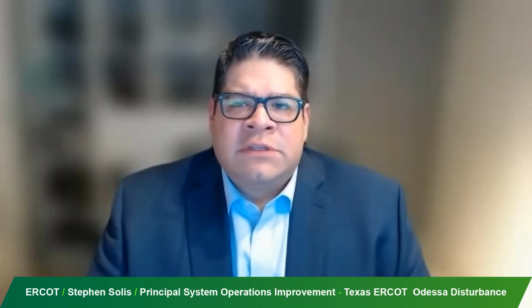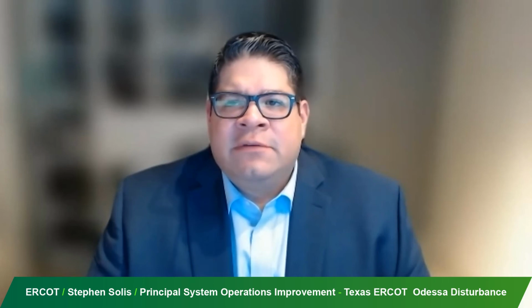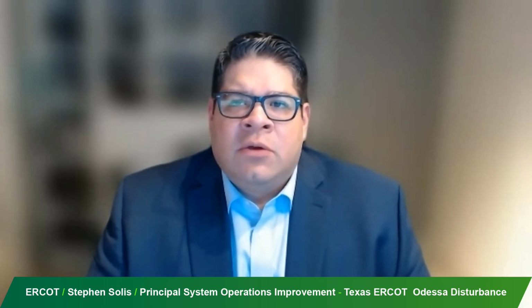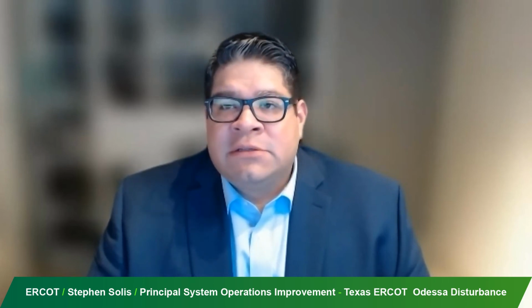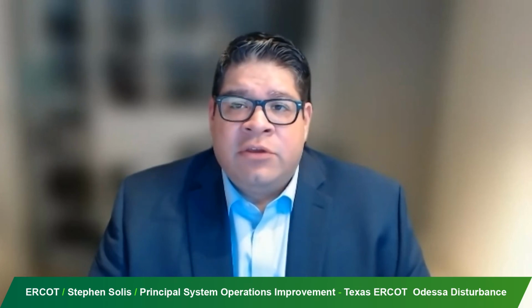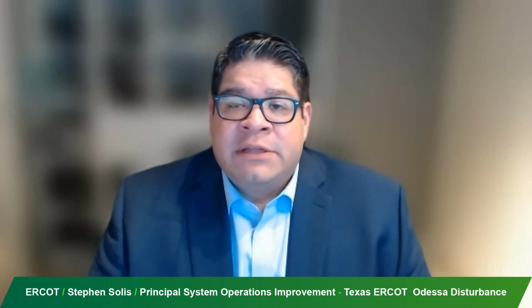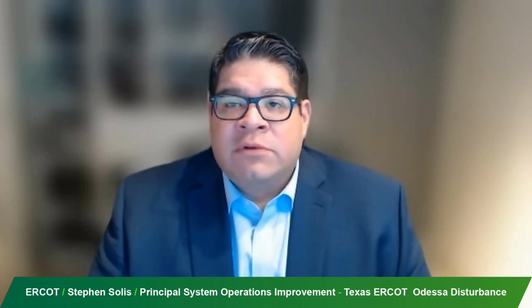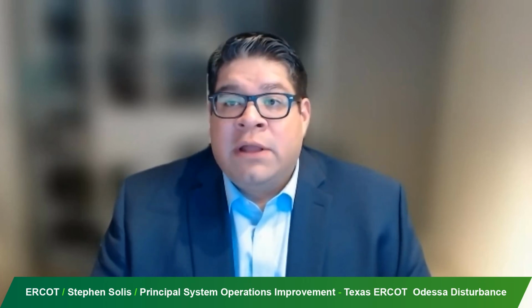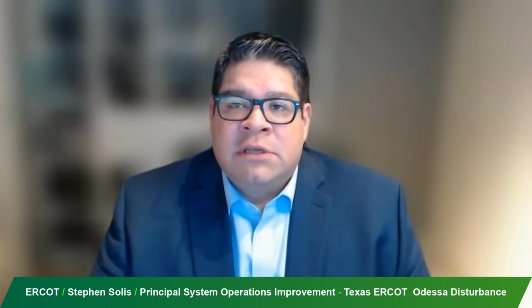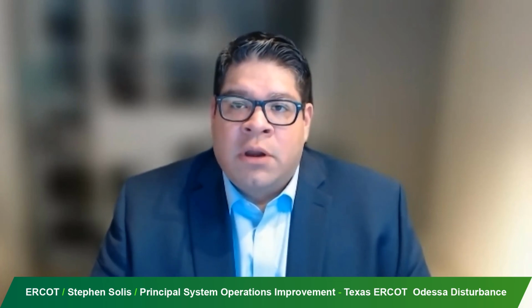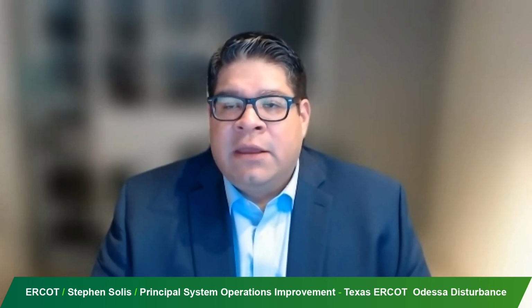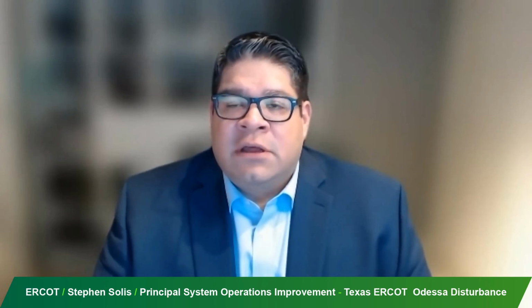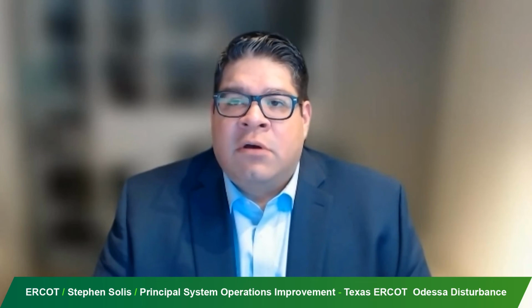Really, it was over voltage. The frequency failures that we saw were really poor measurements. They were not RMS values. And so the measurements, when we saw the high resolution data, saw frequencies much lower than what the system frequency was. And so when we looked into it, their measurement was poor going into the relay. And that's really what caused the under frequency failures we saw.